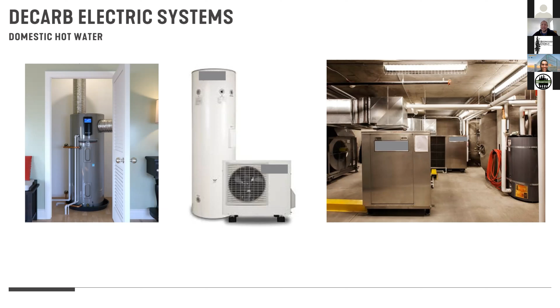So we're all used to 410A and 134A. Those I would say are now very quickly going to become legacy refrigerants as we try to move down to lower GWP refrigerant-based refrigeration cycles. So right now, a lot of folks are moving into R513, especially on the domestic hot water side. We can make hotter water with R513. But R32 is a readily drop-inable, if you will, replacement for 410A. And so with half the GWP, it's sort of a stepping stone, I would say, towards getting to our ultimate goals of getting down to natural refrigerants with a GWP of 1 or 0.